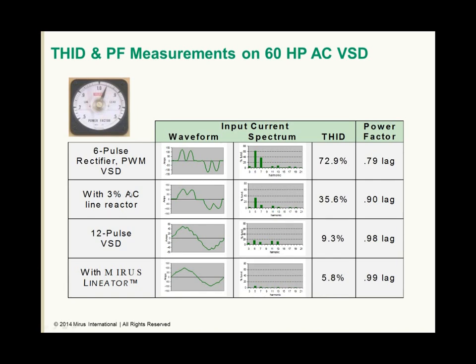When we add a 3% AC line reactor to this same variable speed drive, it broadens the current pulse slightly. By doing that, it makes it a little bit more sinusoidal, which lowers the current harmonics. In this case, we've essentially dropped the current harmonics in half, so we now have about 35% THD. So line reactors can lower the harmonic content, but they are limited in their effectiveness. Power factor is now increased to 0.9 due to the reduction in harmonics.